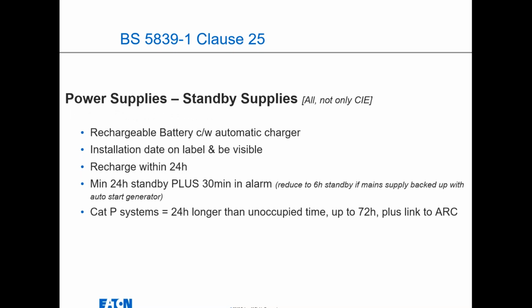Again, power supplies, standby supplies: you've got rechargeable batteries if you've got an automatic charger. The installation date should be visible. Recharge within 24 hours. We talked about the 24-hour standby plus 30-minute full alarm. That can be reduced to 6 hours if the main supply is backed up with an auto start generator. Again, that would be considered if you know that in the building. And category P systems, 24 hours longer than the unoccupied time, up to 72 hours. And obviously you've got a link to the alarm receiving center.